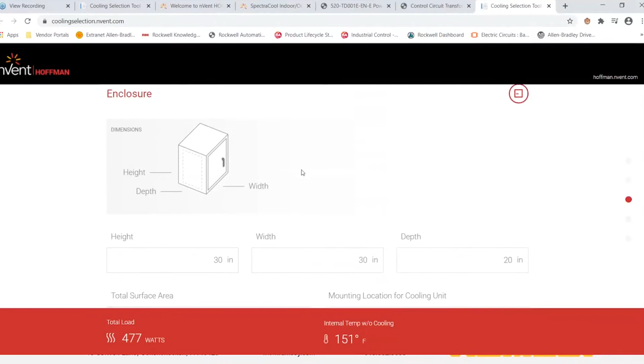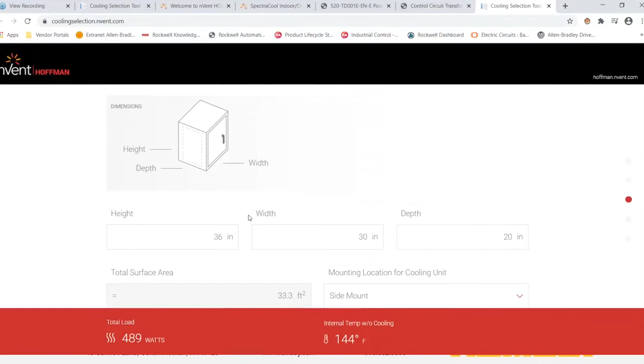So this is the new website. You can either Google Hoffman cooling tool, nVent cooling tool, or remember the website, coolingselection.nvent.com. Up top, language, region, and measurement settings stay the same, Celsius or Fahrenheit, BTU or watts. I typically keep it in watts because most user manuals, like VFD manuals, measure power dissipation in watt loss, so it's easier that way. For this example, I have a 30 by 30 by 20 enclosure, but you can change those, and it'll update the total surface area.